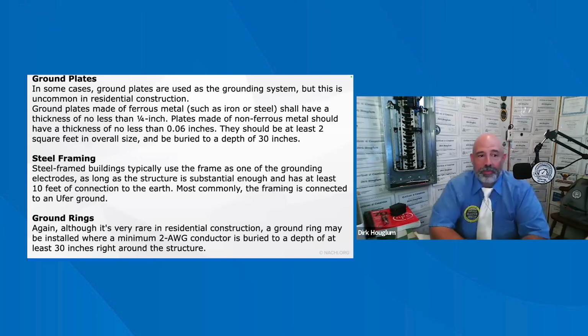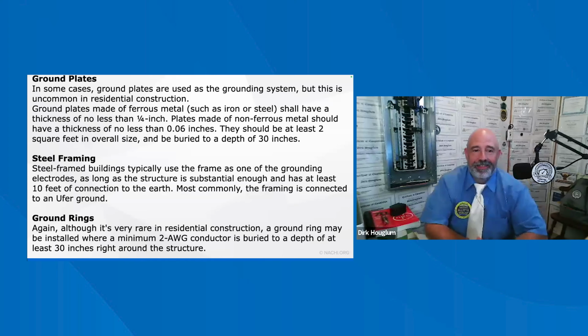Okay, grounding plates, you're probably not going to see too many of these, but they have to be at least 1/4 inch wide and they should be at least 2 foot square around that. Steel framing: now, steel framing buildings have to be grounded as well. And a lot of them are bonded into the electrical system if you have a steel building and electrical.